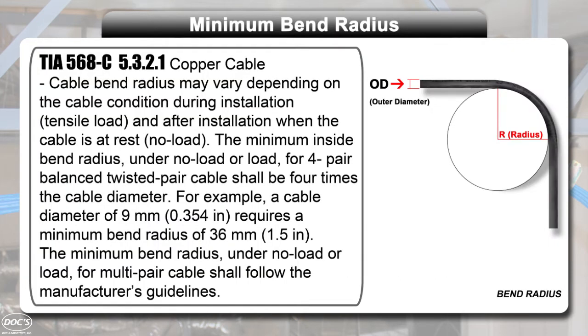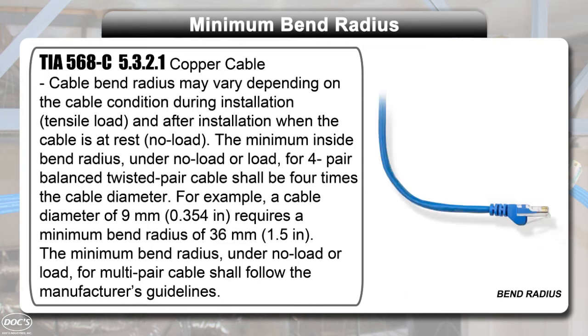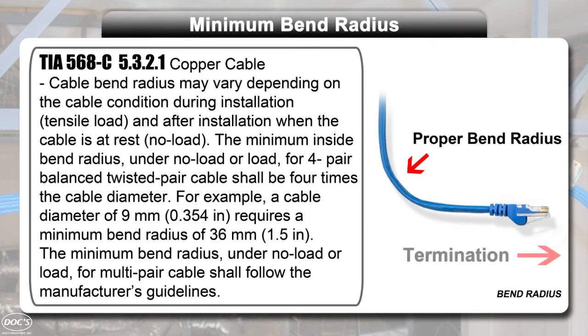Bend radius refers to the minimum radius that a cable can be allowed to bend without damaging the cable. All changes of direction on a cable run should be gradual and smooth whenever possible. For UTP cable, TIA requires a minimum inside bend radius of four times the diameter of the cable. It is always the responsibility of the installer to ensure that proper bend radius is maintained during a cable run and at termination.